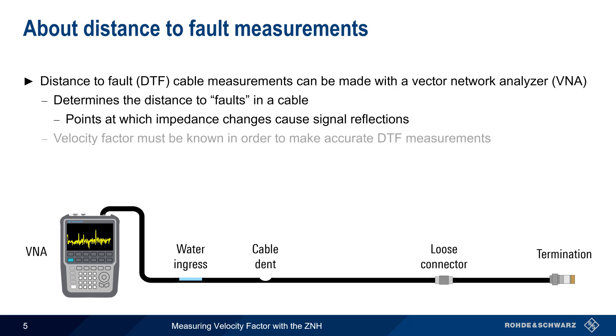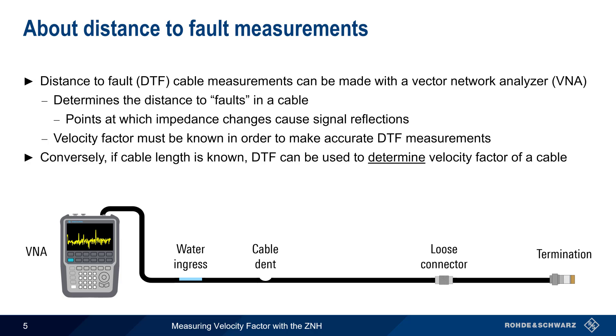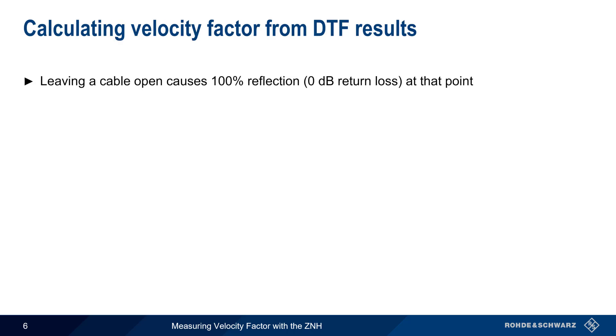The velocity factor of the cable must be known in order to make accurate distance-to-fault measurements. Conversely, if the cable length is known, a distance-to-fault measurement can be used to determine the velocity factor of a cable, and this is done by creating a large fault at the end of the cable. Leaving the end of a cable open or un-terminated will cause all of the transmitted signal to be reflected from that point back towards the source.